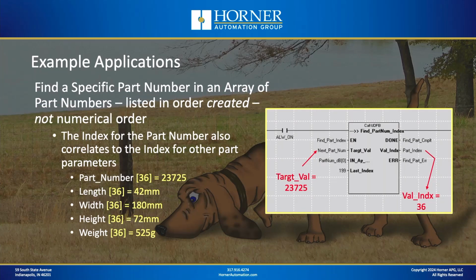To help you do that and to illustrate what I just talked about, here is a view of a user-defined function block in ladder in this case, where we are performing a data find operation. We're looking for a specific integer value that represents a part number from an array of data. Once we find the index where it is found in that array, which in this example on the screen is an index of 36, then we know that we can retrieve, using that same index, the length, width, height, and weight of that particular part number from other arrays that are correlated to it. That's just an example of one case when you might want to search through a list of data to find a specific value.